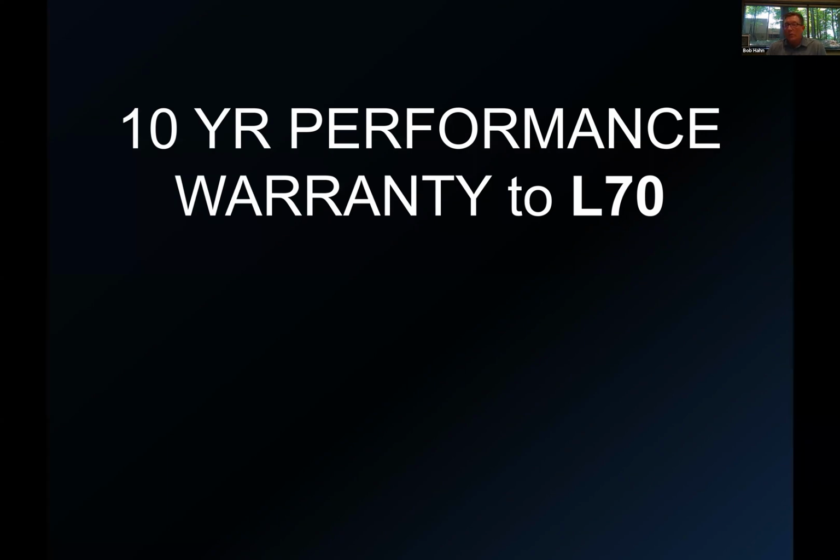I tell the story also that recently we pulled down a wall pack off the back of our building that was put on when we've been here 11 years. 11 years ago, we installed it and turned it on, and we never shut it off. So 6 months ago, we took it down and sent it off for another photometric testing, and we only lost 27% of light output in 10.5 years. And again, that was using very pre-XRC LEDs. They don't exist anymore. They've gone way past that in thermal design and efficacy design. But even using that type of fixture, our thermal process made it so that we can back up this warranty.